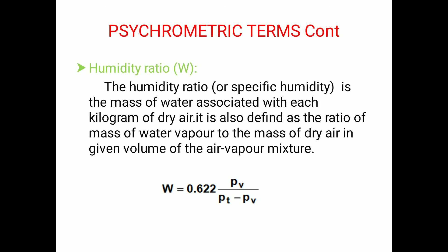Mathematically you can write the humidity ratio W equal to 0.622 PV divided by PT minus PV. And we already know PV is the pressure of water vapor at given temperature and PT is the total pressure. So the next term is the dew point temperature. If unsaturated moist air is cooled at constant pressure, then the temperature at which the moisture in the air begins to condense is known as the dew point temperature of air.